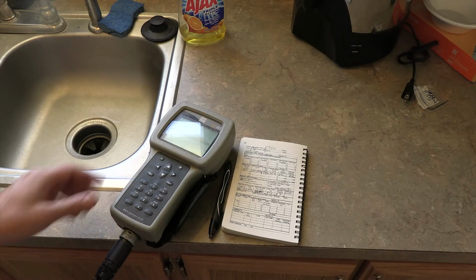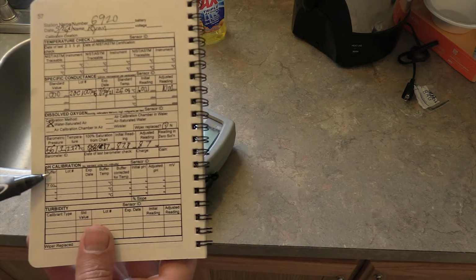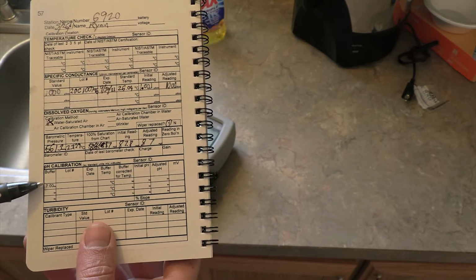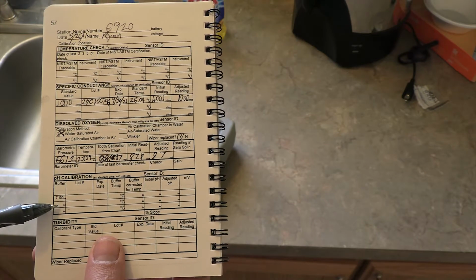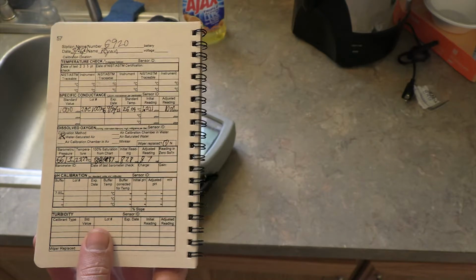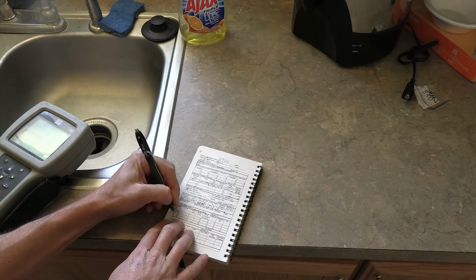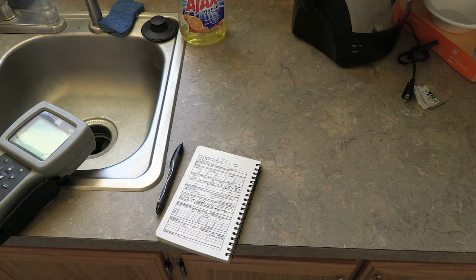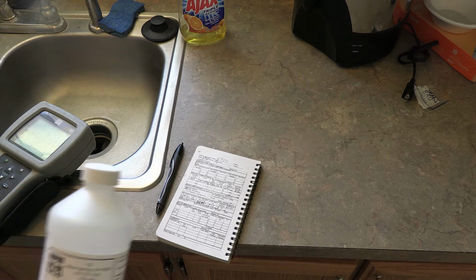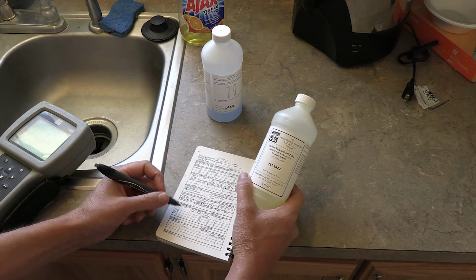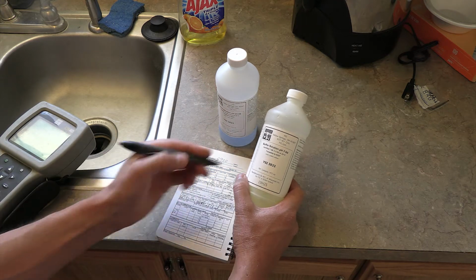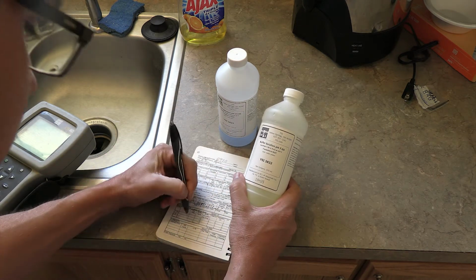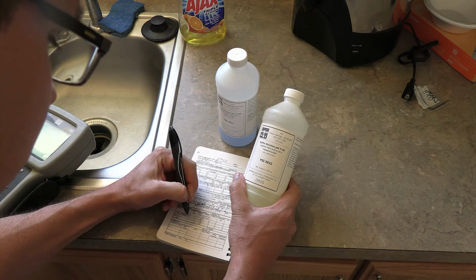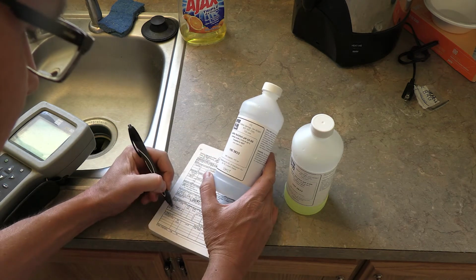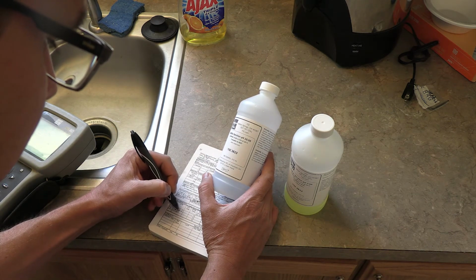Okay, let's keep going here with the calibration of the pH. We have 2 pH solutions we need to use, 7 and 10. Let's put in 10. Let's pull out all these solutions here. We can leave the rinse solutions by the probe, and let's put these in. Let's get the lot numbers. We don't need the number of the YSI type. So for 7, we got 19H2S. For 10, 19H1T.